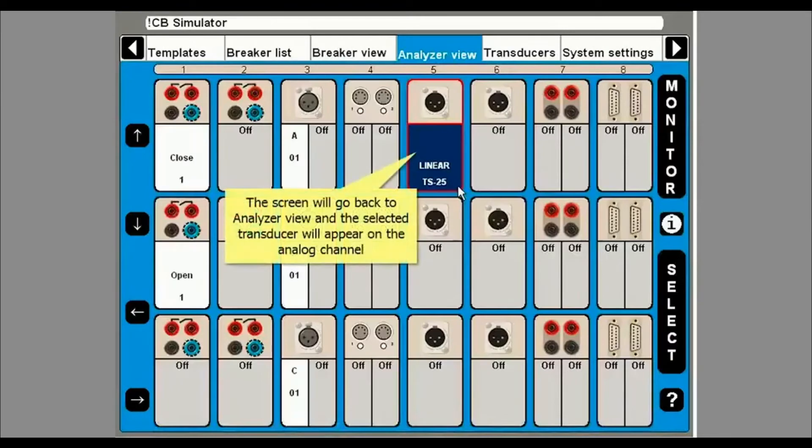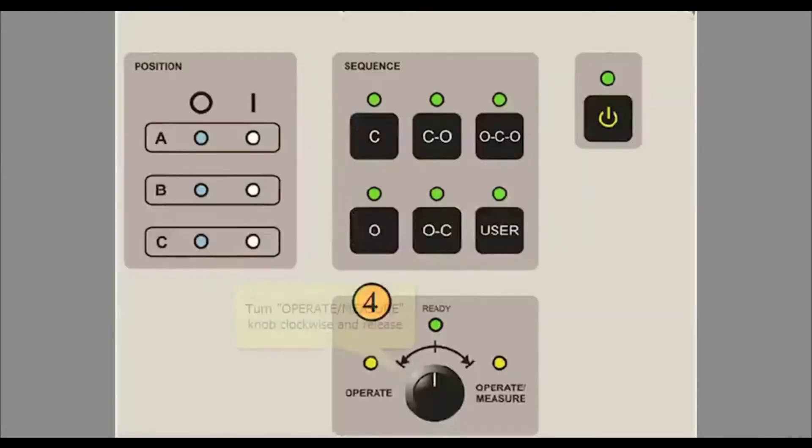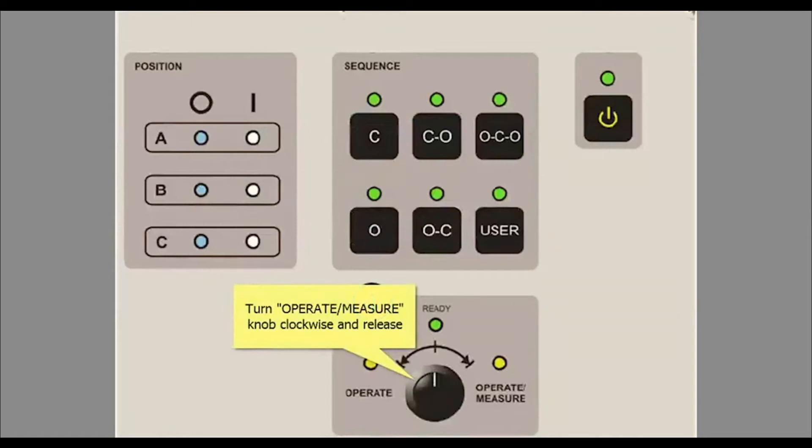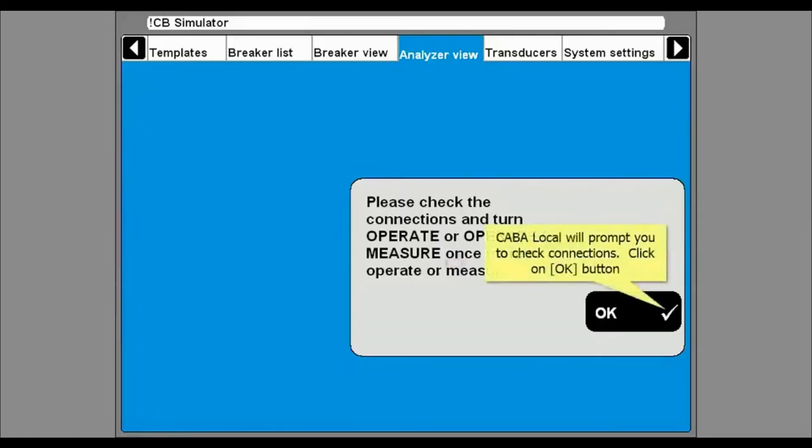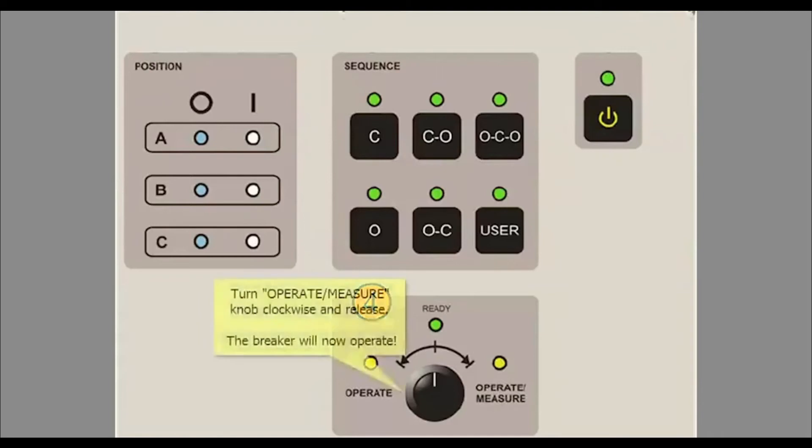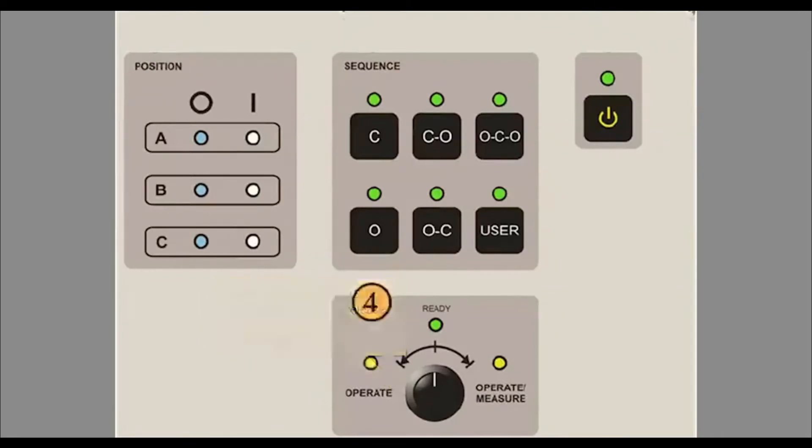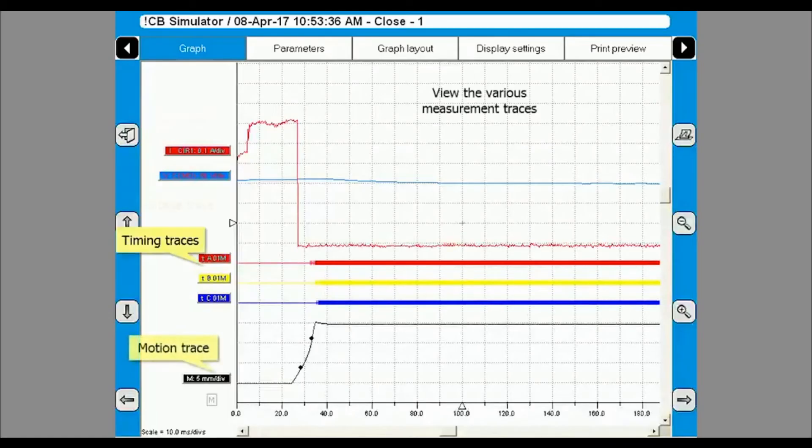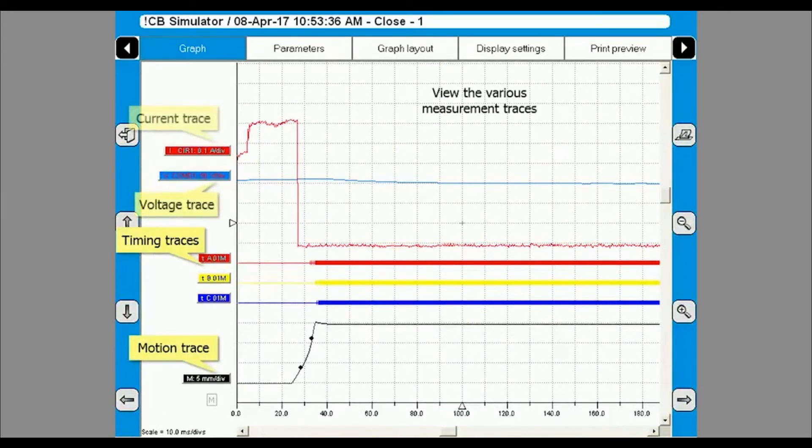You are now ready to test. Turn and release the operate and measure knob clockwise. This will bring up a window asking you to check the leads. Click OK. Turn and release the operate and measure knob clockwise again and the circuit breaker will operate. The various graphs of motion, timing and other important data will appear.